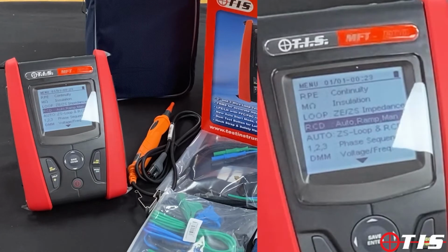Again, from a time saving point of view, the unit has an automatic RCD testing function, as well as being able to operate on a single shot mode. It will do an automatic RCD test where it will carry out all the 6 tests that we would normally require, but we can also tag on the ramp test onto the auto test as well, so we can tell it to do an automatic test and ramp, just so we can confirm the actual tripping current of the RCD. As an addition to that, the unit will test standard AC RCDs as well as the new A-type, so again, future-proofed tester.